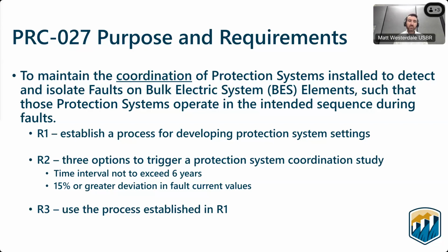As part of this process, they give you 3 options in R2 that would trigger a coordination study. The first option is to do it on some sort of time interval, as long as it doesn't exceed 6 years. The second option is if you see a 15% or greater deviation in your fault current values in your short circuit model. The third option is just a combination of the 2 previous ones.